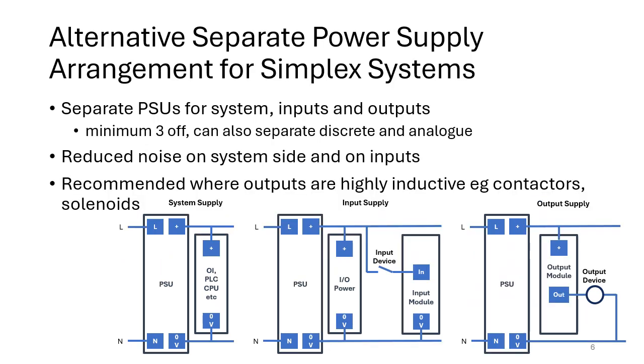Now, there's still a possibility of interference from the outputs to the inputs. That's less of an issue if you've got mostly discrete I/O all running at 24 volts DC, but it is common to see crosstalk and interference coming from DC outputs going into analog inputs. So if you ask for very high analog accuracy, then you may prefer to isolate the input and the output supply. So now we're up to 3 power supplies. We've got at least 3.